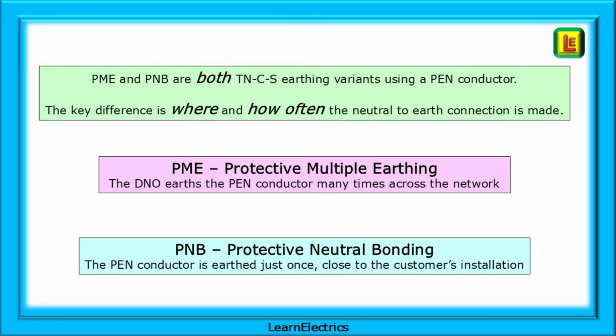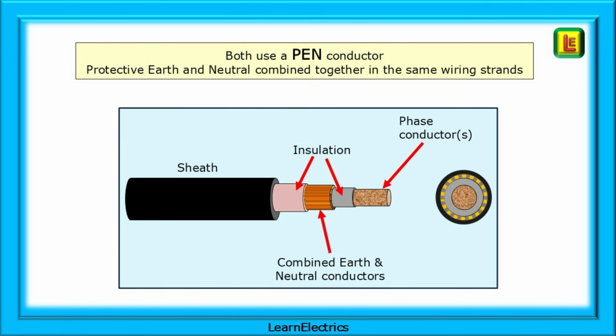Number 2, PME is protective multiple earthing, where the DNO earths the PEN conductor many times across the network. Number 3, in a PNB system, or protective neutral bonding, the PEN conductor is earthed just once, close to the customer's installation. And number 4, both use a PEN conductor, where protective earth and neutral are combined together in the same wiring strands, and the PEN conductor is used differently in each system. The simple drawing below shows the phase conductor core and the combined earth and neutral conductors making up the next shell, lots of insulation and a PVC sheath.